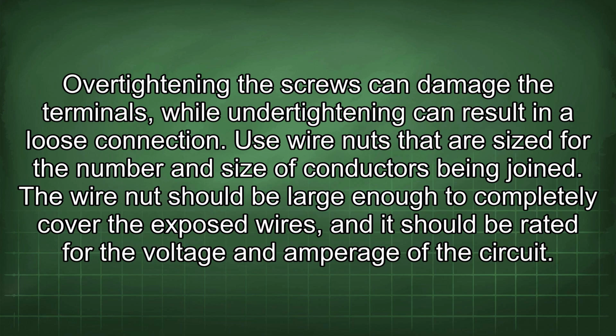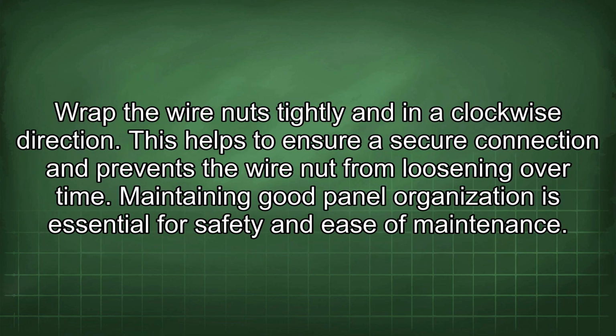Use wire nuts that are sized for the number and size of conductors being joined. The wire nut should be large enough to completely cover the exposed wires, and it should be rated for the voltage and amperage of the circuit. Wrap the wire nuts tightly and in a clockwise direction. This helps to ensure a secure connection and prevents the wire nut from loosening over time.